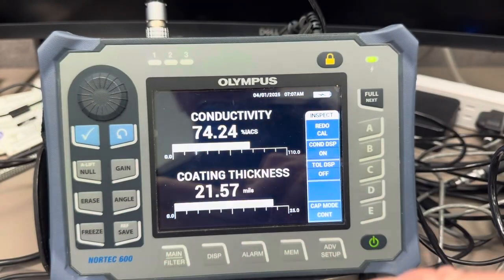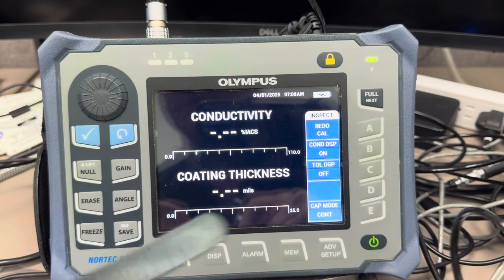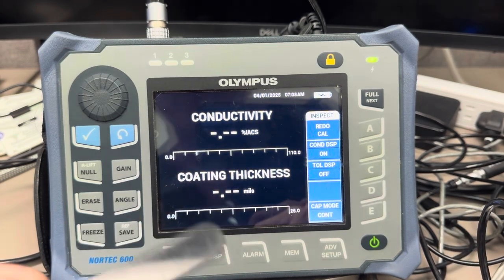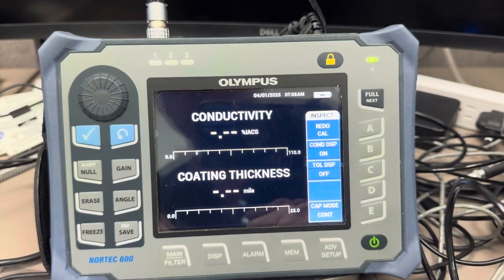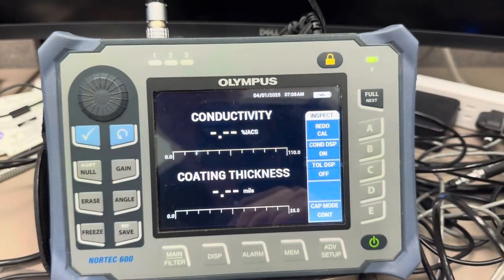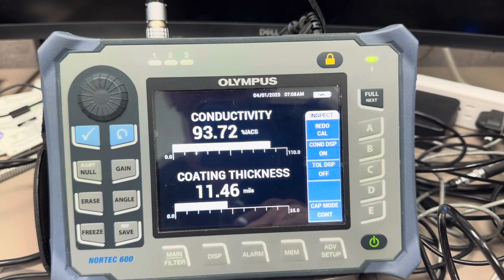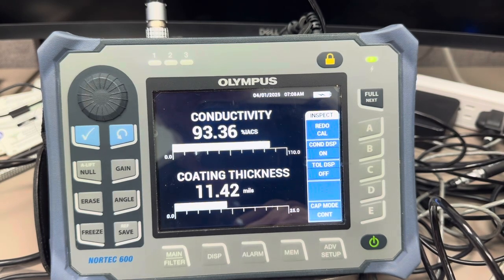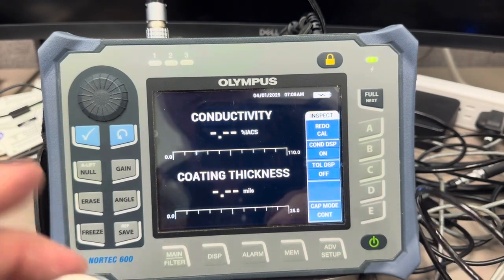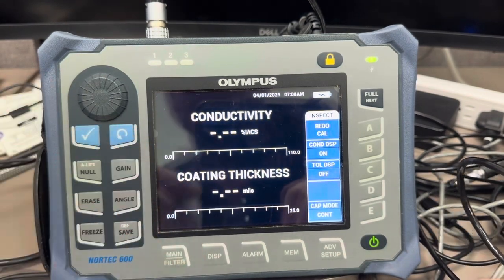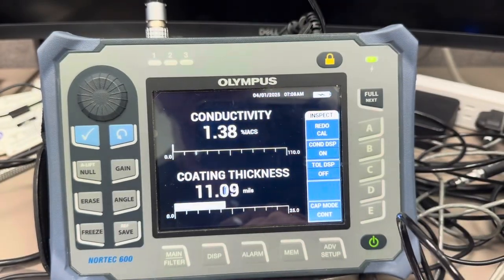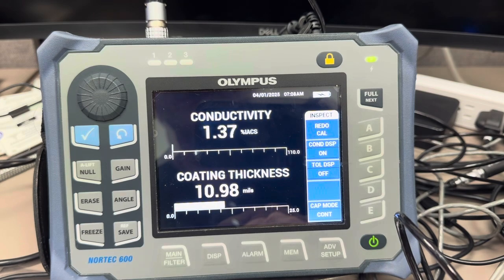Let's go over to the copper. Let's just try the copper without a shim. We're getting 100 and something. And now we'll try the 12.5 mil shim on the copper. It's going to look like that. Look at that, almost 12 mils. Conductivity dropped a little bit, but what do you expect? Okay, let's try the 12.5 mils on 1% IACS. Look like that. 1.3, 1.4% IACS and 11 mils. I'd say that's pretty close.